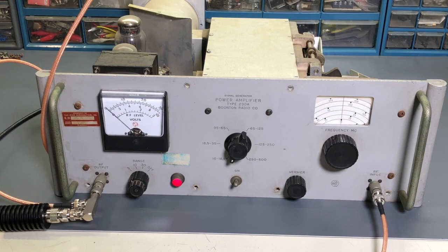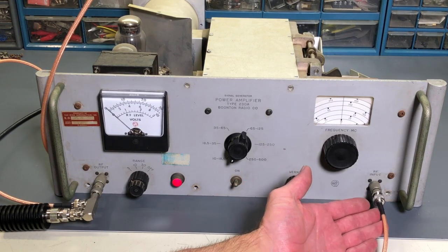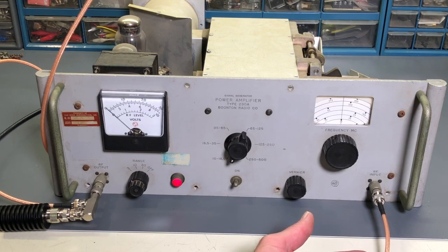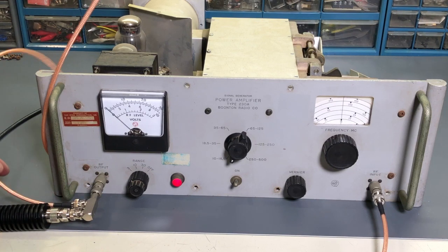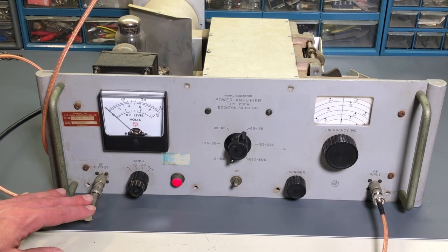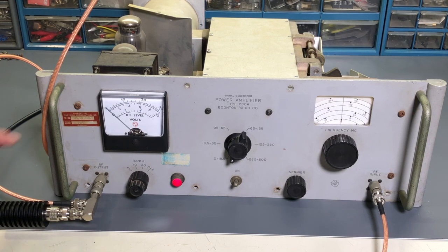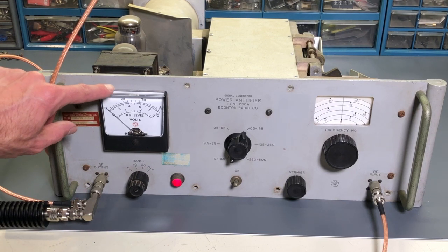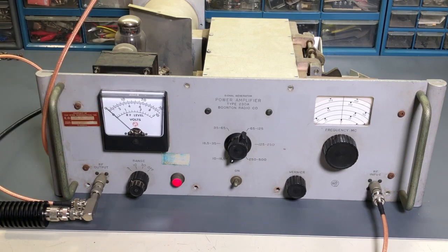Alright, here we are looking at the front of the amplifier, and on this side you can see the RF input. This is coming from the signal generator. On the RF output side, it goes into a T connection, and we have the 50 ohm dummy load. This is rated for 15 watts, and it's good from DC to 500 megahertz, so well within the range that we'll be testing here. And then this coax cable goes up to the oscilloscope so that we can monitor the output waveform and the output level. So we'll be watching for an indication on the RF voltmeter here, and we'll want to see if this corresponds to what the oscilloscope is showing us.